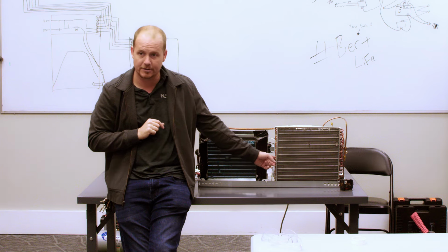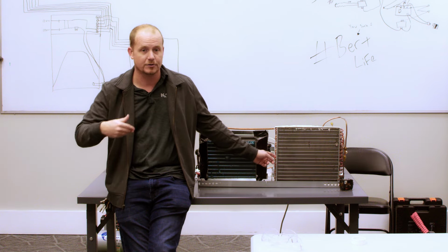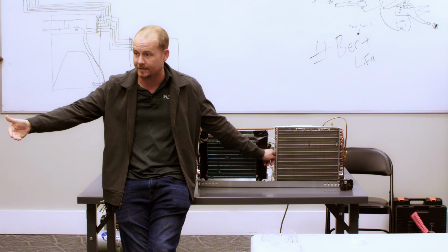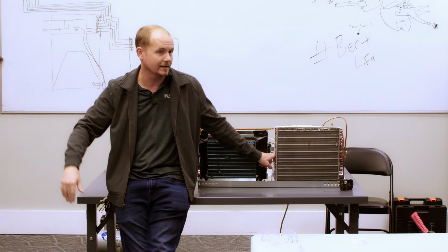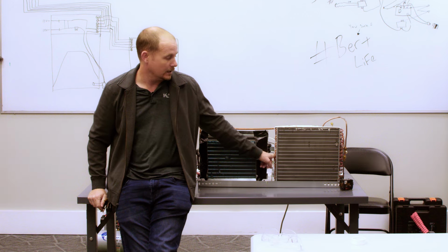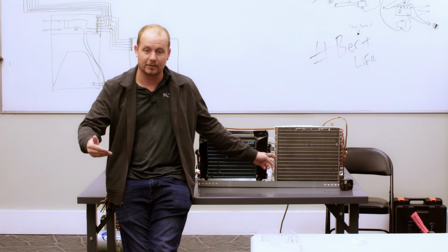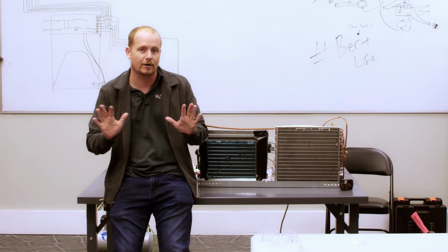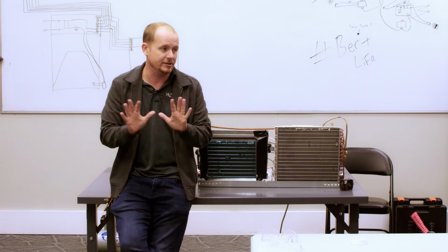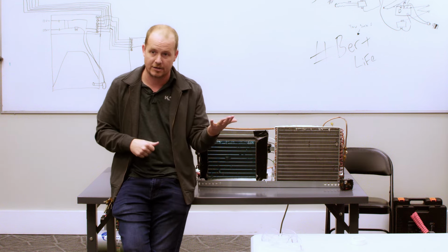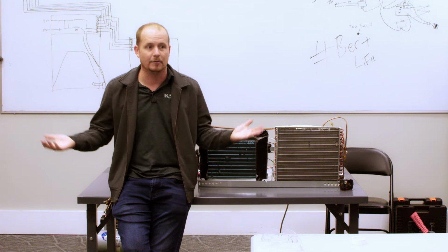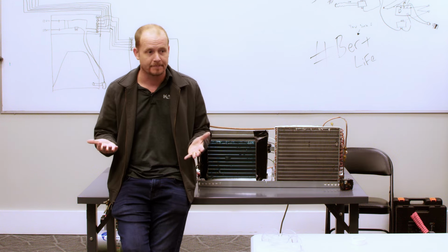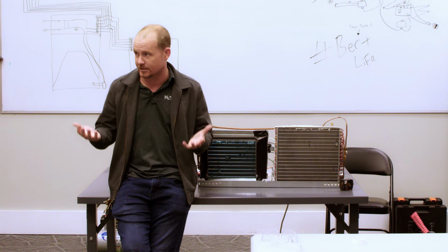So our condensing temperature compared to our outdoor temperature is what we call condensing temperature over ambient, or CTOA is what we typically call it. And then if we just compare our liquid line temperature to outdoor temperature, that's what we call approach. But all of those are giving us some reference for how this system is doing in terms of both compression, mass flow rate, how much refrigerant is moving through the system, and charge. So it tells us a lot.